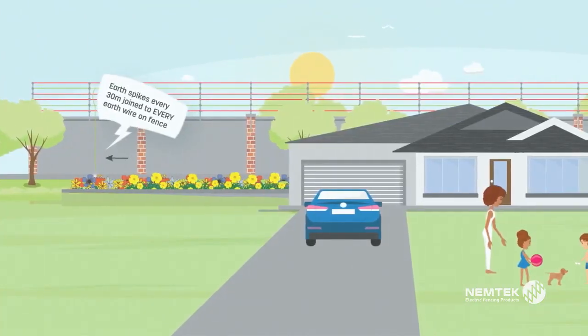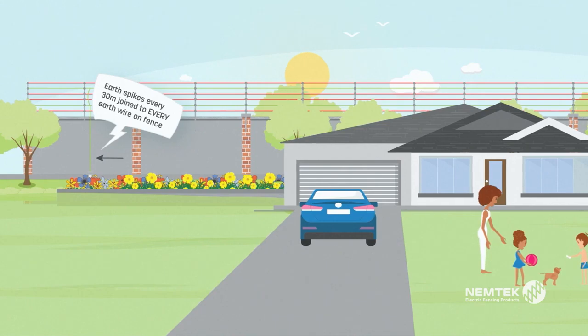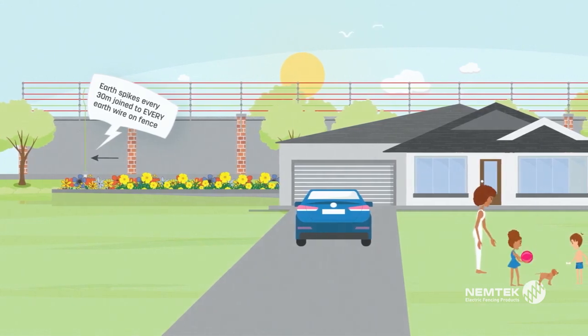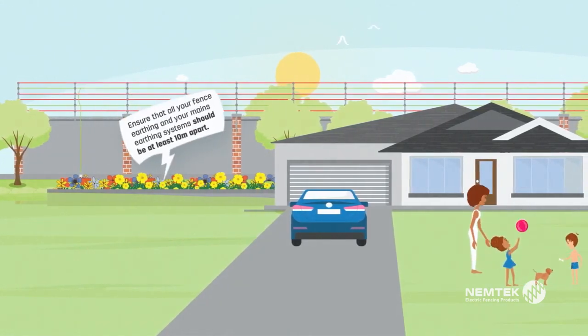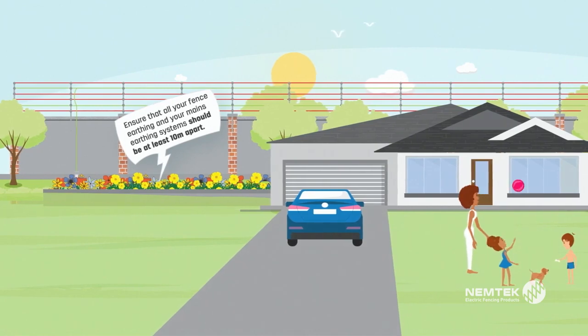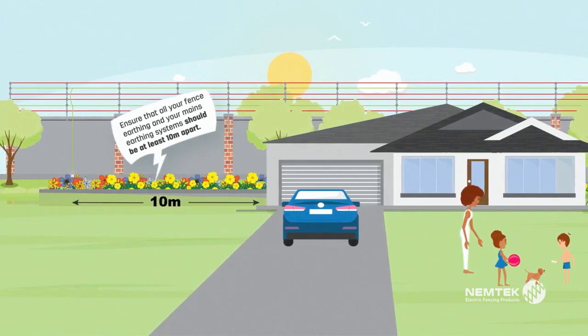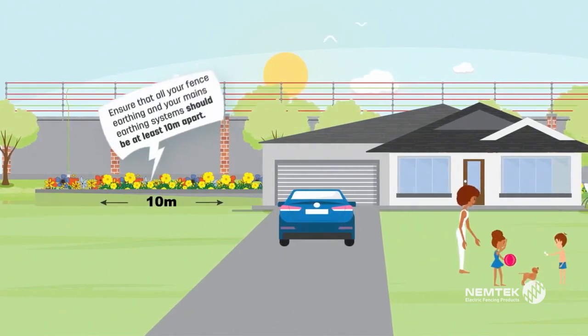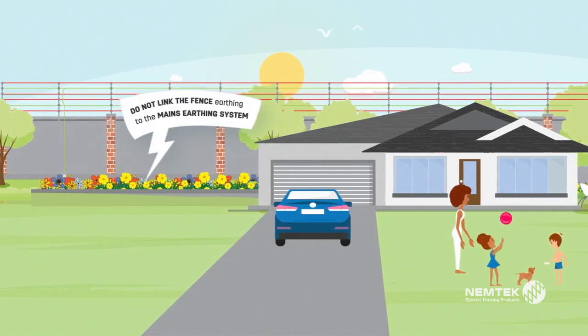Ensure effective earthing along the complete fence by placing earth spikes no more than 30 meters apart. Your fence earthing and mains earthing systems must be at least 10 meters apart. Do not link the two together.